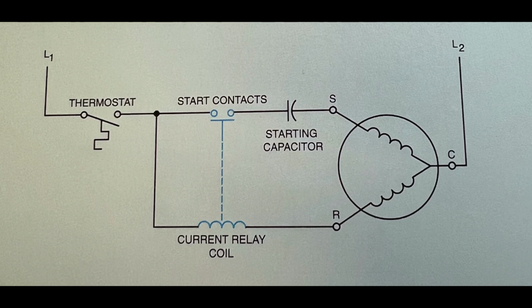When the thermostat contact closes, power is applied to the run winding of the motor. Since the start winding is open, the motor cannot start. This causes a high current flow in the run winding circuit. This high current flow produces a strong magnetic field in the coil of the relay, causing the normally open contacts to close and connect the start winding to the circuit. When the motor starts, the run winding current is greatly reduced, allowing the start contacts to reopen and disconnect the start winding from the circuit.